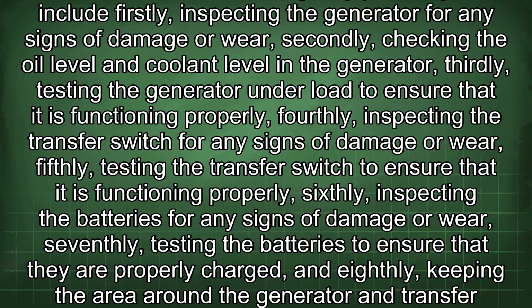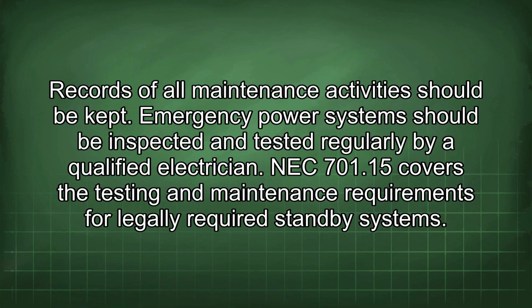Fifthly, testing the transfer switch to ensure that it is functioning properly. Sixthly, inspecting the batteries for any signs of damage or wear. Seventhly, testing the batteries to ensure that they are properly charged. And eighthly, keeping the area around the generator and transfer switch clean and free of obstructions. Records of all maintenance activities should be kept. Emergency power systems should be inspected and tested regularly by a qualified electrician.